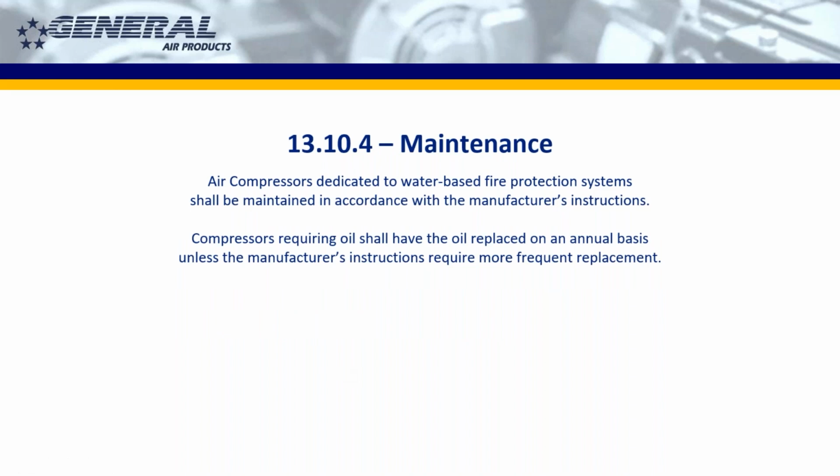13.10.4 is saying that compressors that require oil have the oil replaced at least on an annual basis. While the standard says annual, remember the standard's about a minimum requirement.